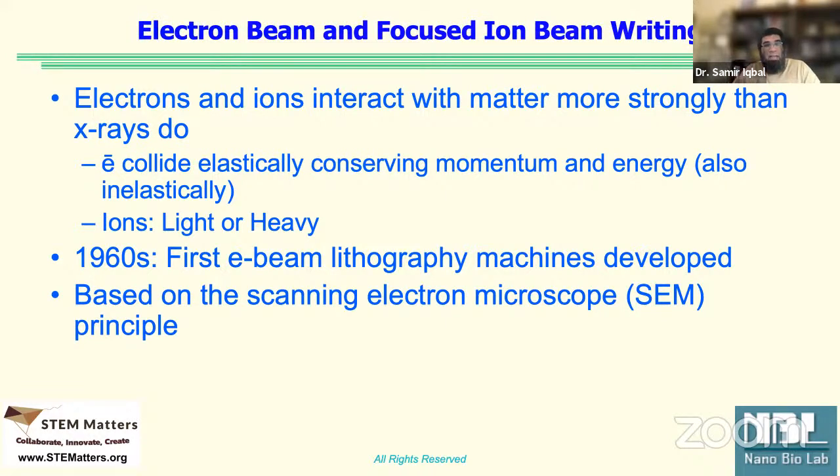It has to be in a clean lab. For electron microscopes, the requirements are slightly different. When you are dealing with the very fine electron beam, even if a person walks outside the door of the lab, the vibration of that walking can cause your beam to flicker.